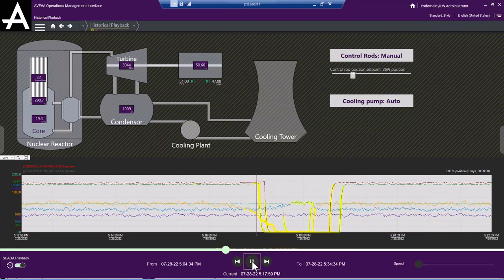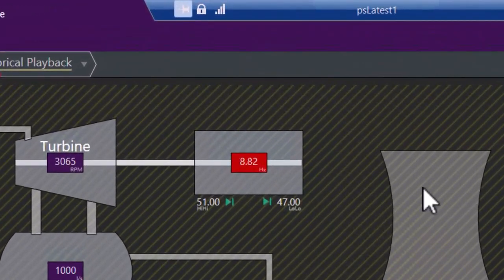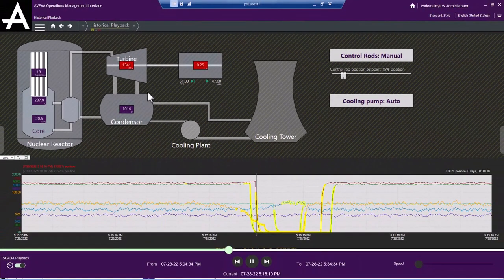We automatically detect if there is no history available for specific attributes. We'll switch back and show the live values on the screen. Now, this can lead to some confusion for things like alarm limits, etc. that may have been historized or may not have been historized. And to indicate that we are showing a live value during historical playback, we've got a little indicator there that's a status icon. You can modify the status icon to display something else if you wanted to, or you can just leave it off.